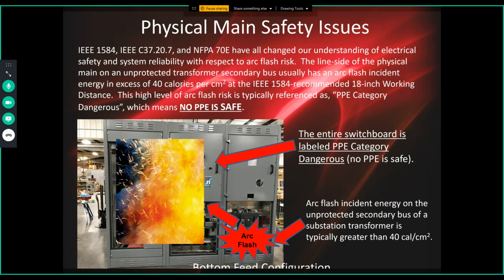So what I'll see, and this is quite common, is two different arc flash labels on this same low voltage switchboard. On the line side of the switchboard, of that main breaker, I'll see a dangerous arc flash category, and then they'll take the overcurrent protection of the main circuit breaker and calculate a lower arc flash incident energy on the remainder of the switchboard.